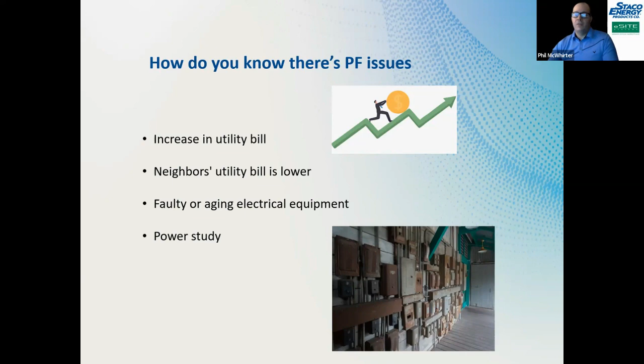So now you say, hey, I might have poor power factor. What can I do about it? Large industrial loads, like motors and pumps, create a situation where your inductive load is lagging behind your voltage. Your voltage is leading current. So to correct this, you need to add some capacitance to close that gap.